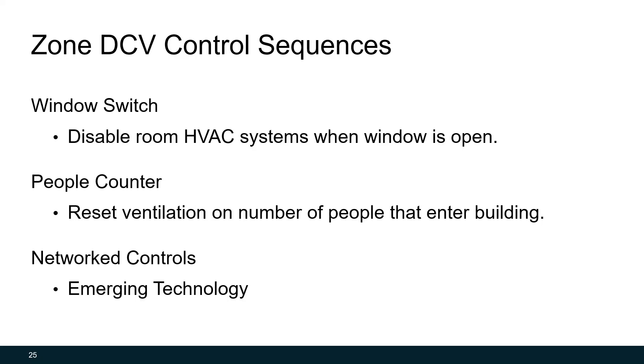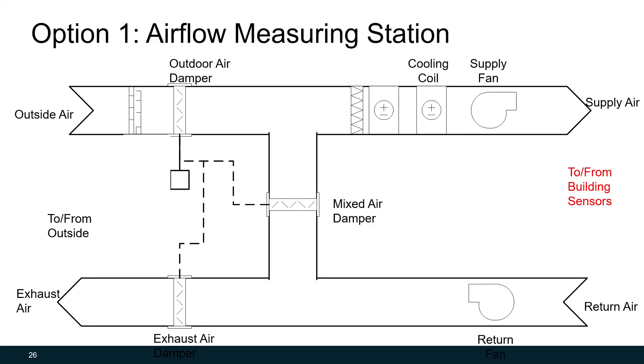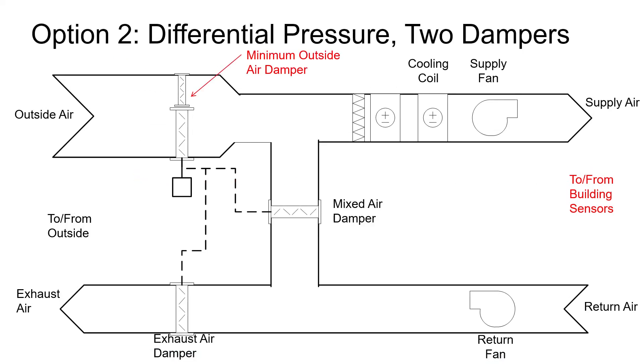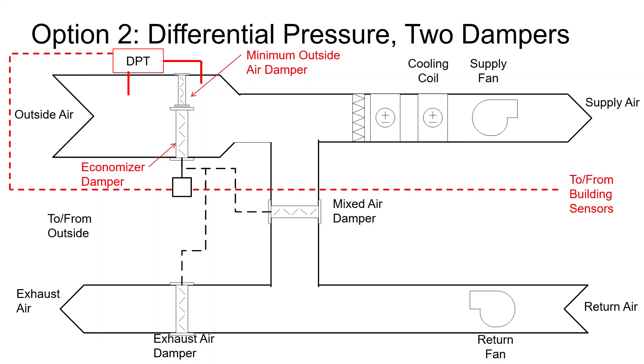We can integrate all of that into our overall DCV control system. At the air handling unit, we want to either use the airflow measuring station to reset outdoor air — resetting it based on all building sensors or the most critical zone — or put in two dampers, one for minimum outside air and one for economizer, based on our differential pressure transmitter, and again reset our set point based on all the zone sensors, either through polling or the most critical zone.